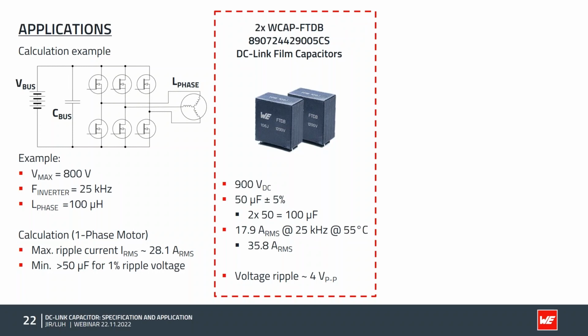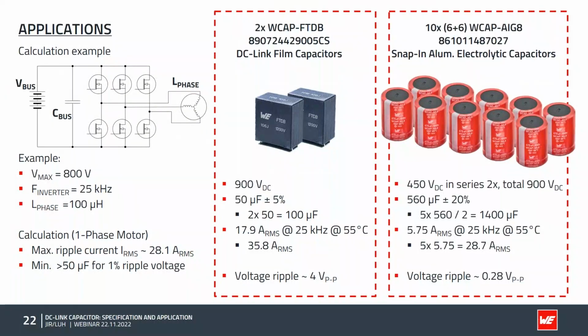So let's see, if we want to use electrolytic capacitors, we have to place many of them. First, we are using 450 volt parts because we only have capacitors up to 550 or 600 volt, and we need two of them in series to get the 900 volt rating. Also, these are big capacitors, and still we are only getting a rating of 5.7 amps RMS, so we need five of them in parallel. In total, we will have 10 cells for a total capacitance of 1.4 millifarad.